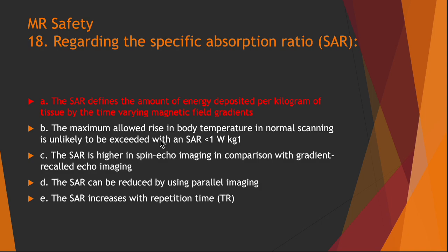The maximum allowed rise in body temperature in normal scanning is unlikely to be exceeded by SAR less than 1 watt per kg.